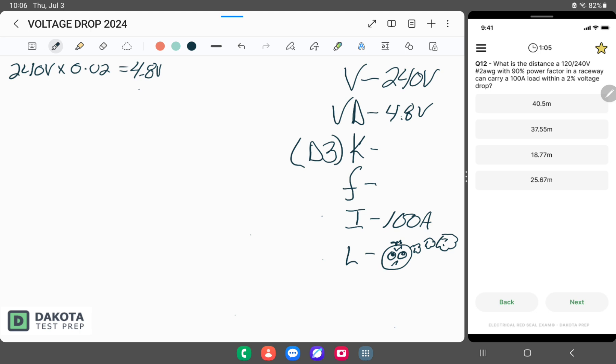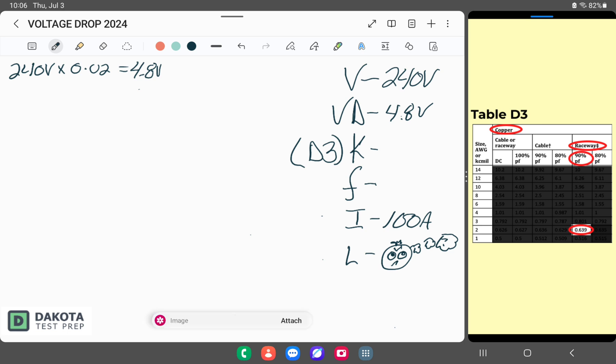Our K factor is based off of the new table D3. With this one, we choose copper or aluminum. If the question doesn't mention copper or aluminum, we always assume copper. This question specifically mentioned raceway, so we're going to use that column. It also mentioned our 90% power factor, so we're going to use that column.